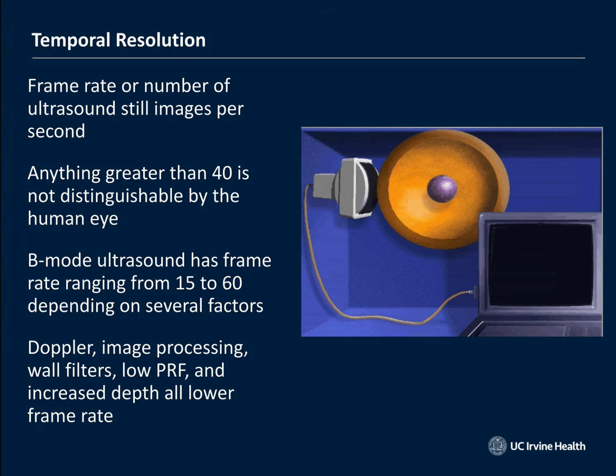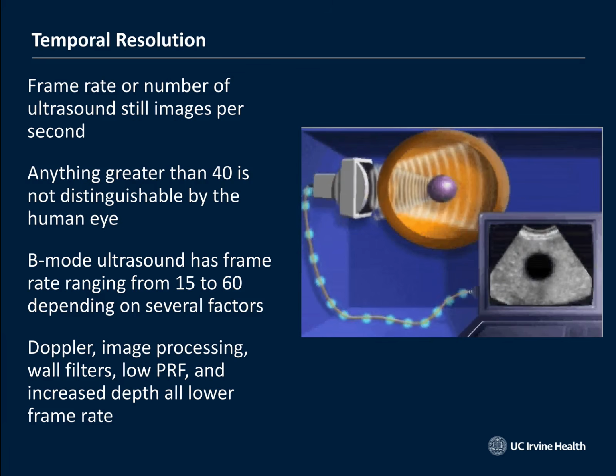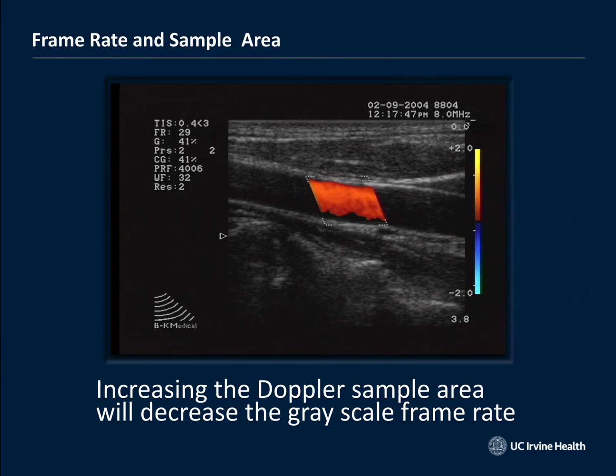When you activate the Doppler, that really slows down your temporal resolution. So the image looks a little bit herky-jerky. What I mean is when you move the probe, the image kind of lags behind it. It doesn't have that high frame rate, real-time image as much. Sound is going into the body, it reflects back out, and then on the screen it's writing those images at a certain frame rate. Adding Doppler slows down that frame rate, and that's called poor temporal resolution. It's the number of frames per second.